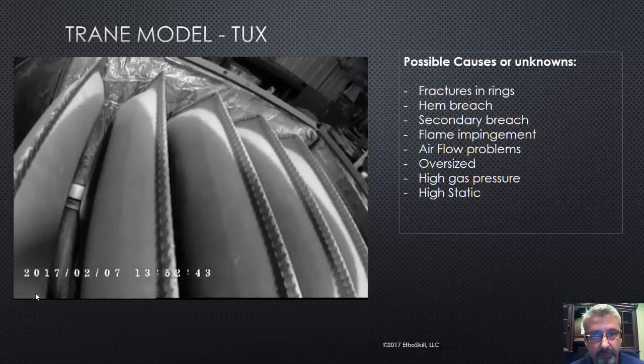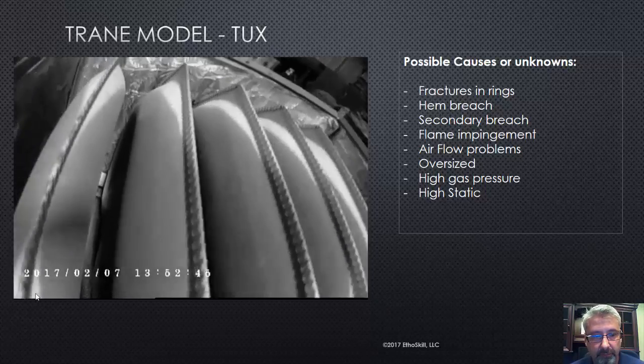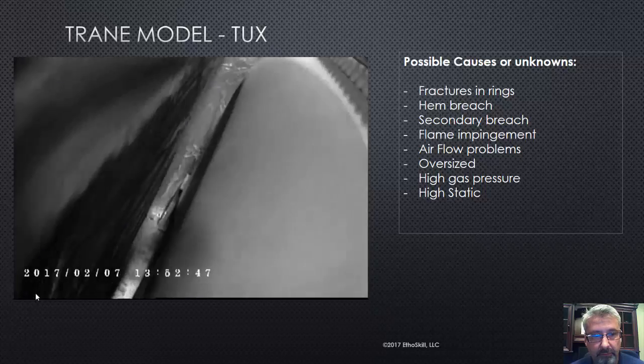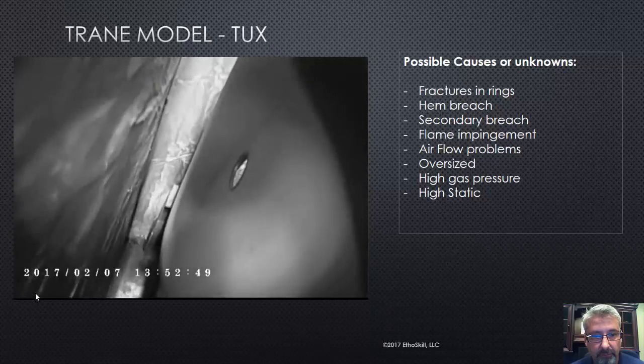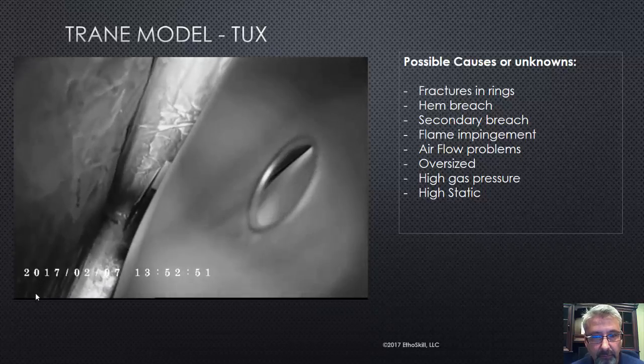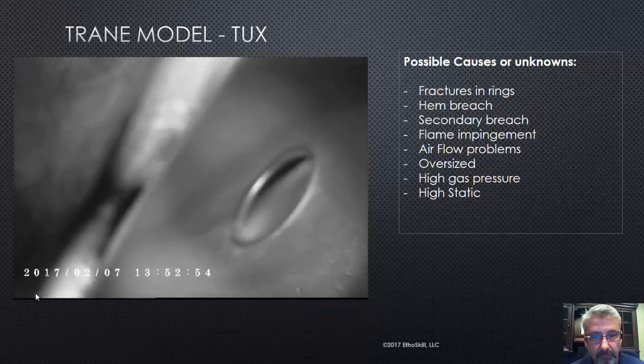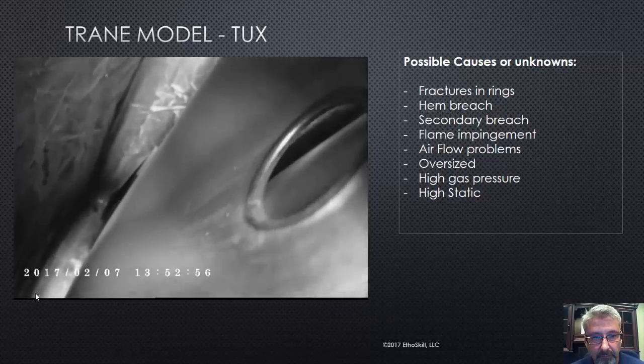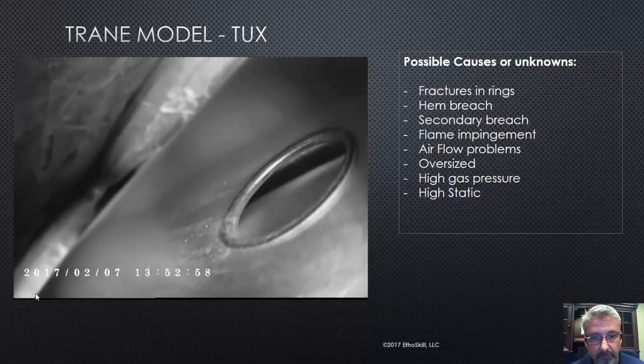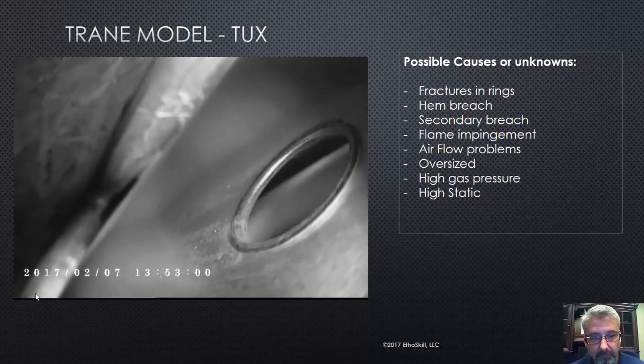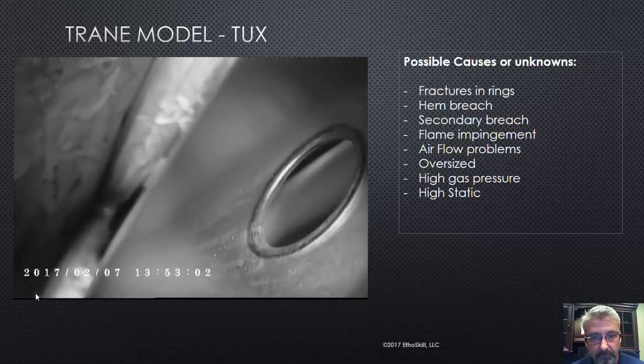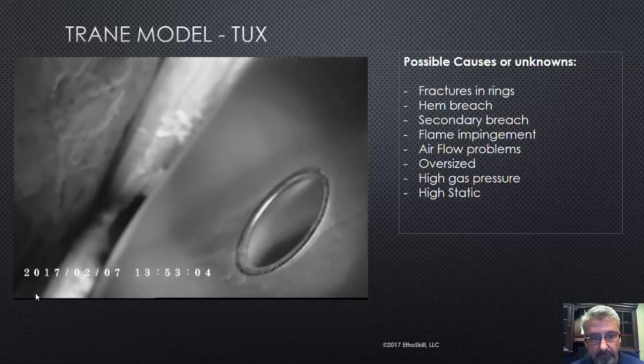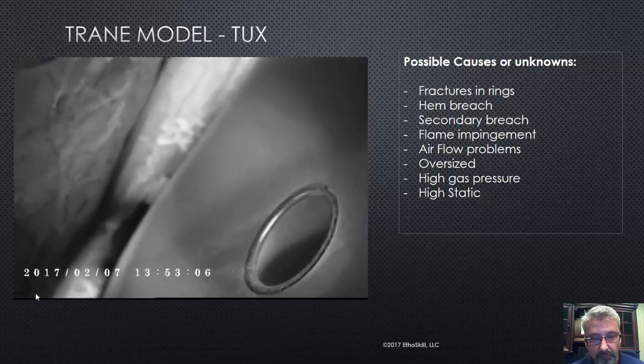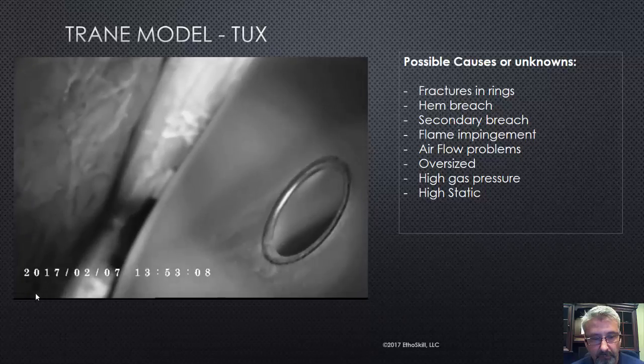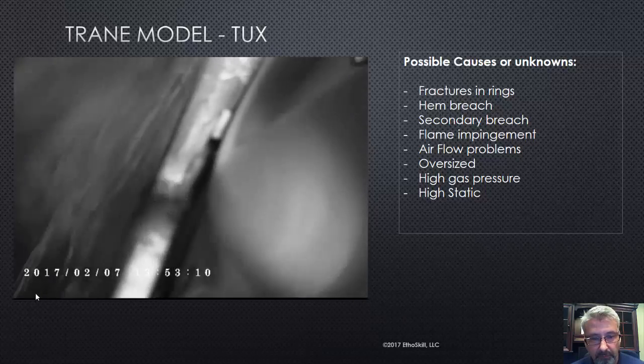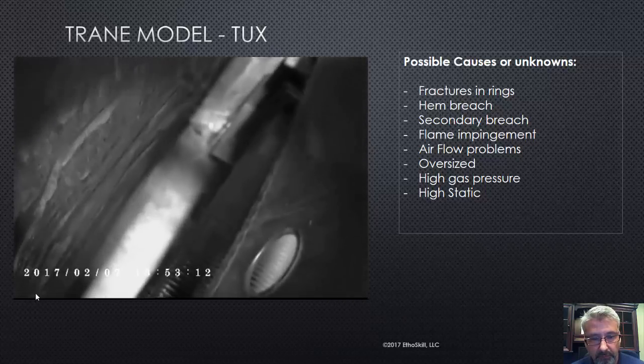In one of the other videos I showed you the TUC model. This heat exchanger is pretty much the same. One of the areas that you want to look on any of the Trane models, you want to look at these rings. Check those rings, and you can run your finger across it. I know some of you are going to say, but there's no plenum on this furnace, no bonnet. I get that. I was a tech for a long time, and I know it's not easy getting your tools into certain places. But the reality is, you've got to look for those rings, or check those rings.